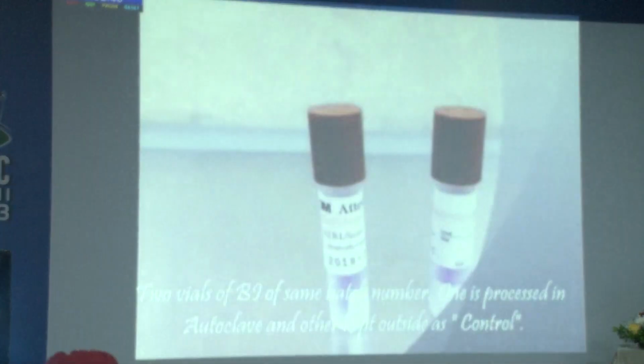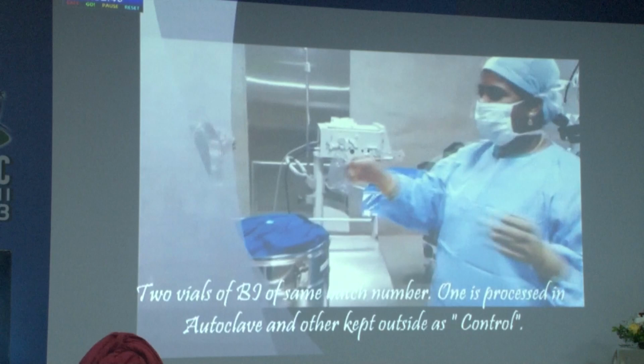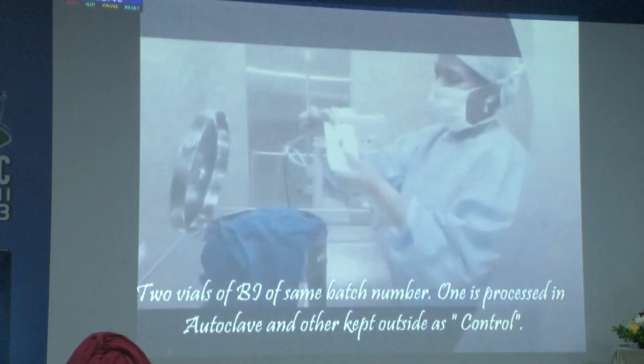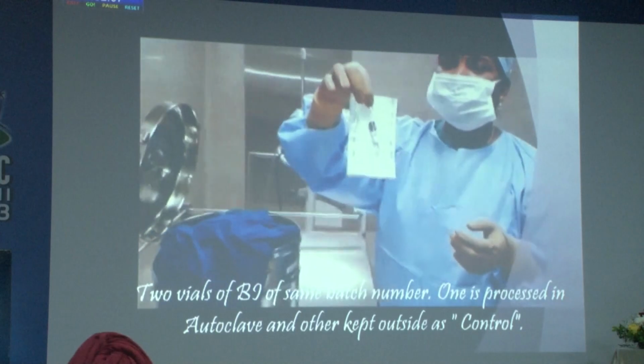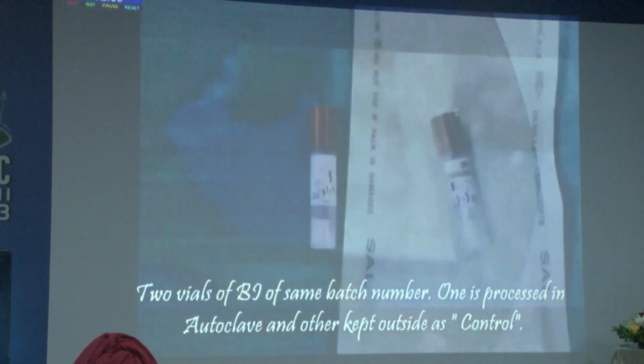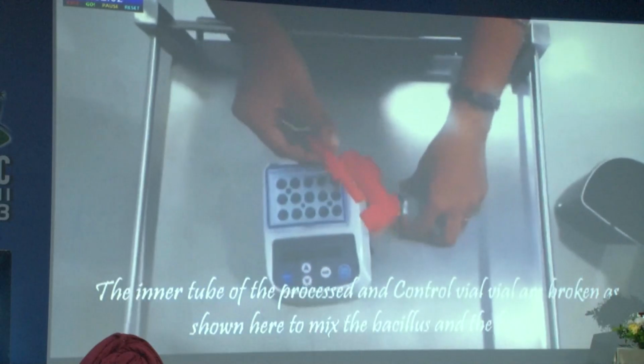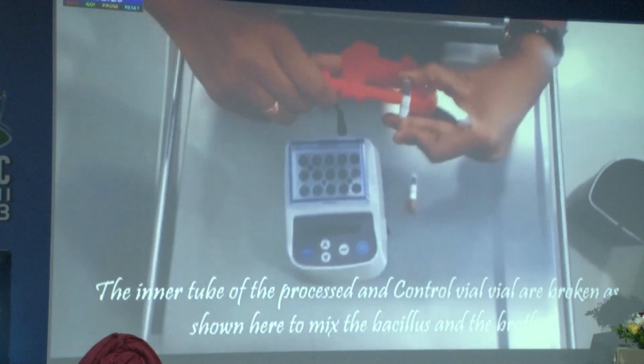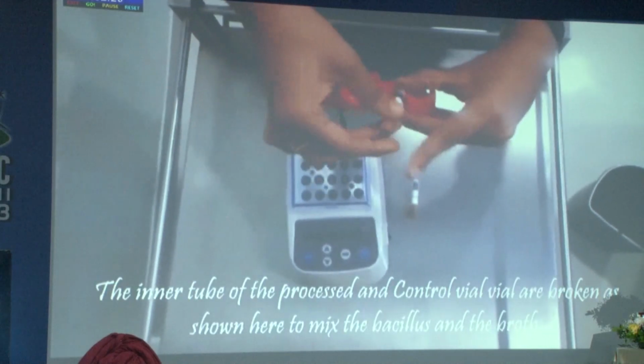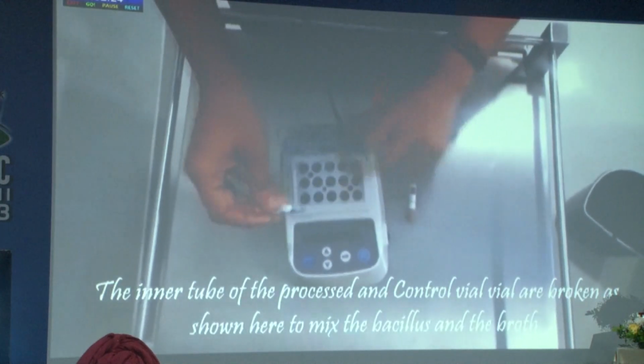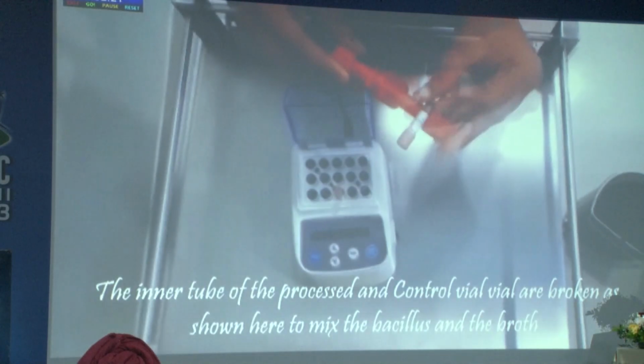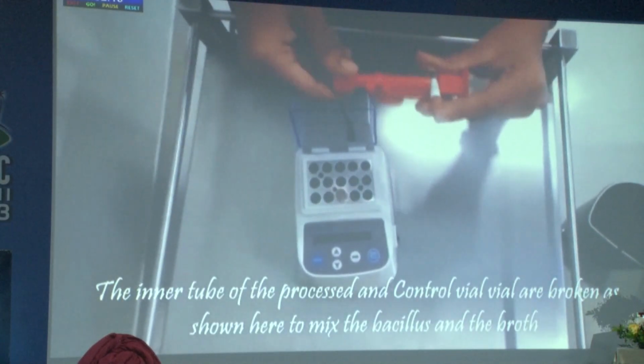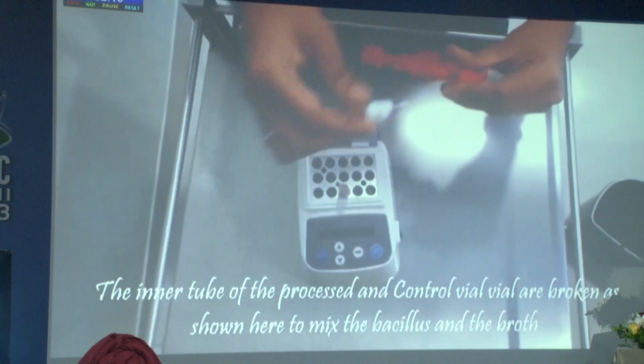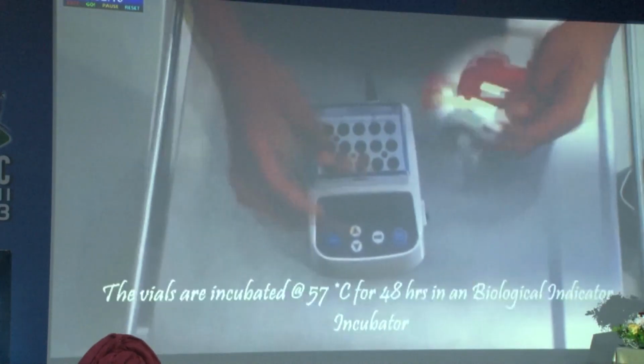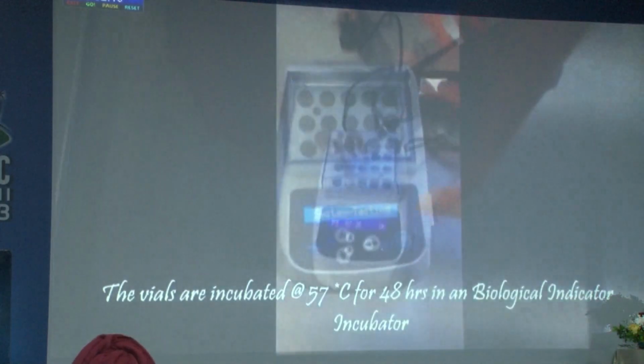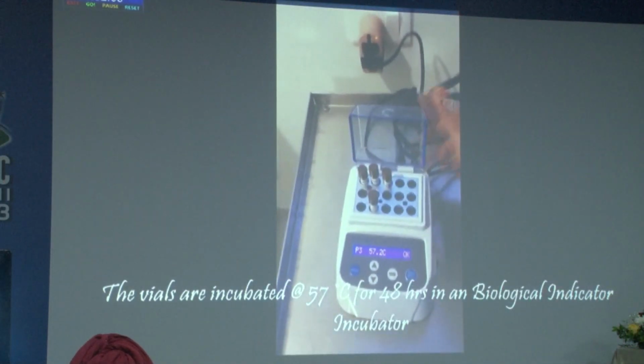The biological indicator, as I told you, has two vials. One is kept outside and the other is kept inside. You remove the processed vial and you have to break the inner vial, which contains the broth and the indicator. Please place them only after breaking it, otherwise you would find all remains violet. So this makes the broth and the bacteria, which is Bacillus stearothermophilus, which is the most heat resistant bacillus, incubated at 57 degrees Celsius for 2 days. Most of the time, you will read the result in 12 to 16 hours itself. The maximum has to be incubated for 48 hours.